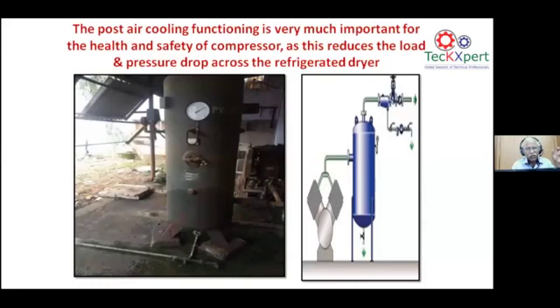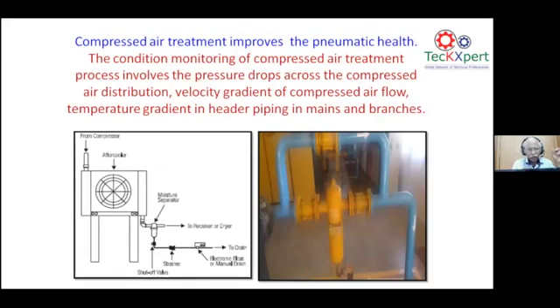Why the moisture separator, like what you use on the steam side, is used on the compressor side also: water is to be removed on the compressor delivery side from the air end. The water separator at the compressor delivery also needs to have the auto drain, and this auto drain has to function along with the receiver's valve, because the water separator is like a baffle plate, where the compressed air with velocity hits the baffle plate and a lot of water is collected. In many industries, the water separator is another neglected area in the compressor house, where a lot of water is collected and not released at all.